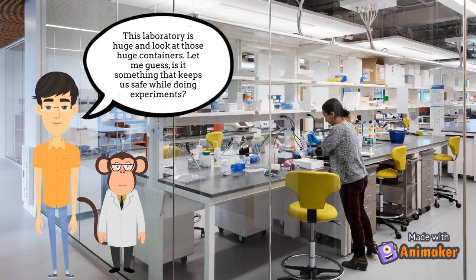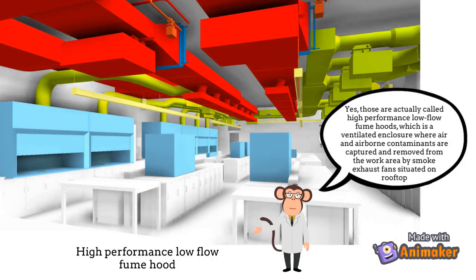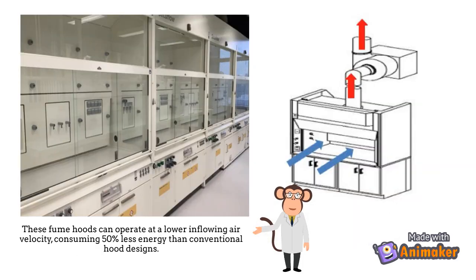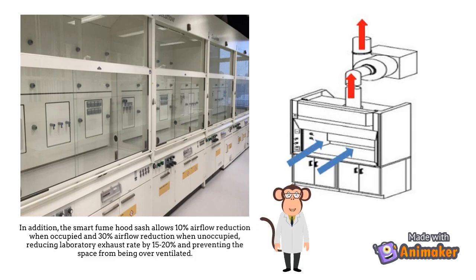This laboratory is huge, and look at those huge containers. Let me guess, is it something that keeps us safe while doing experiments? Yes, those are called high-performance low-flow fume hoods, a ventilated enclosure where air and airborne contaminants are captured and removed from the work area by smoke exhaust fans on the rooftop. These fume hoods operate at a lower inflowing air velocity, consuming 50% less energy than conventional hood designs. The smart fume hood sash allows 10% airflow reduction when occupied and 30% reduction when unoccupied, reducing laboratory exhaust rate by 15 to 20% and preventing the space from being over-ventilated.